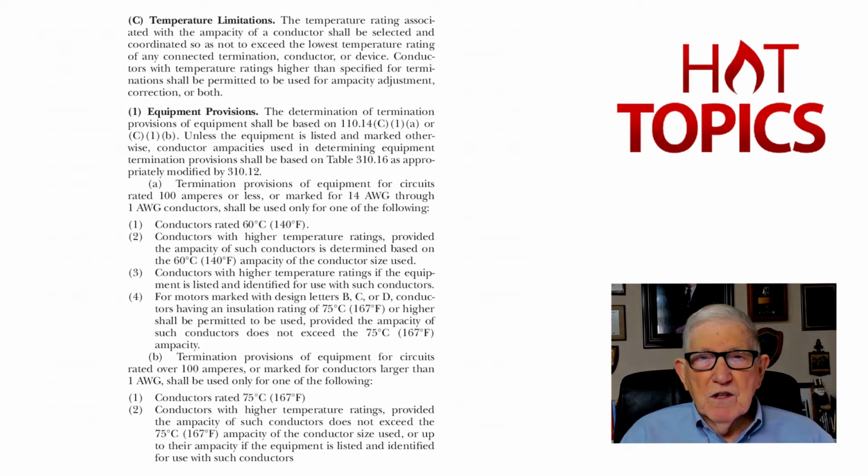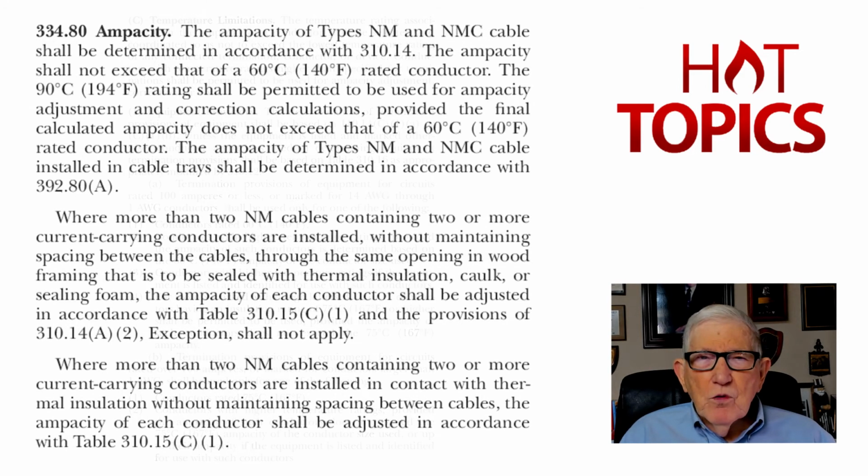We did an illustration and a calculation for a feeder using both derates, but notice we did away in the code with the triple derate. We no longer have that on our backs anymore, where conductors would be so large, in many cases you couldn't even terminate them. Now, I have a section that explains this more to the user of the code, especially a beginner, and that's 334.80.